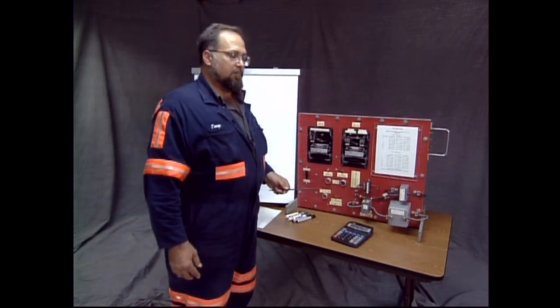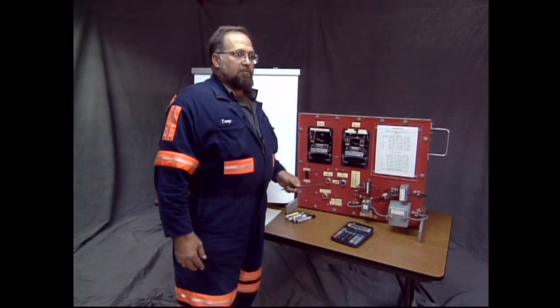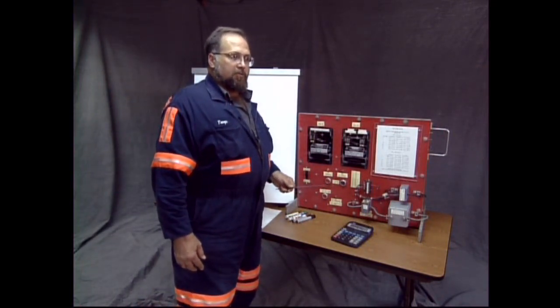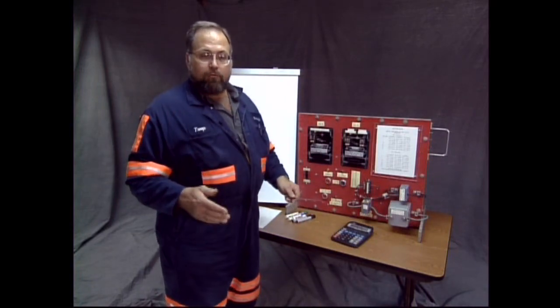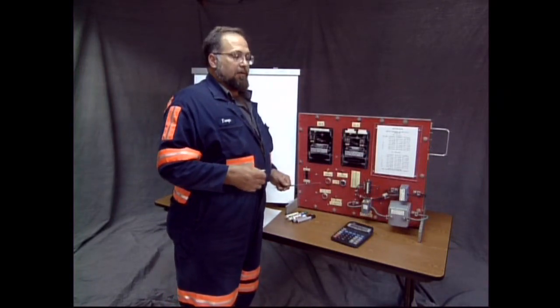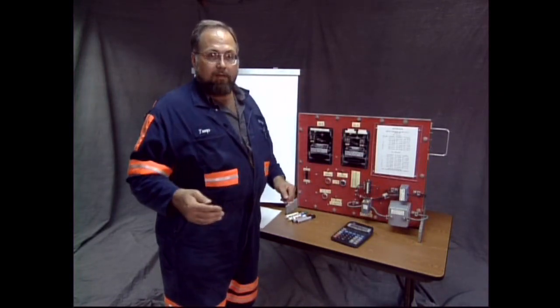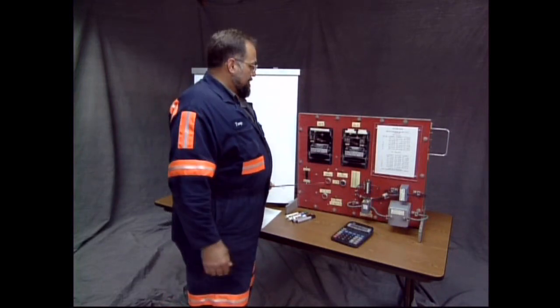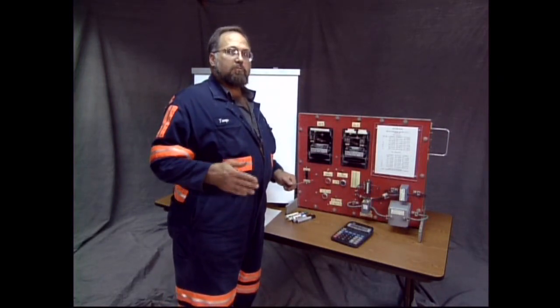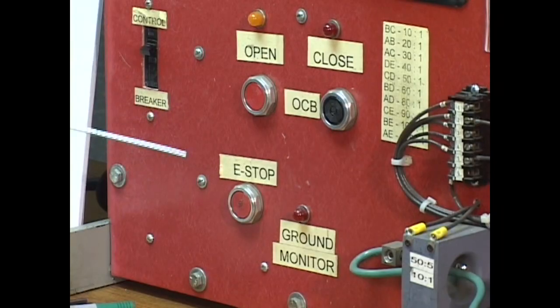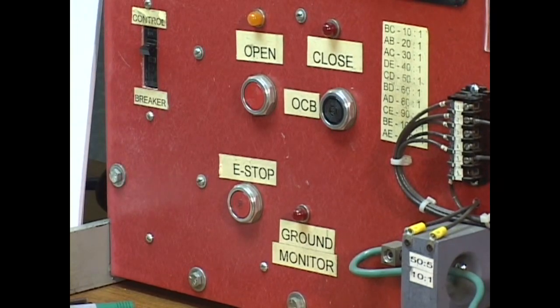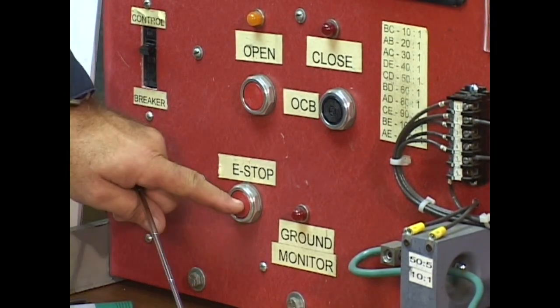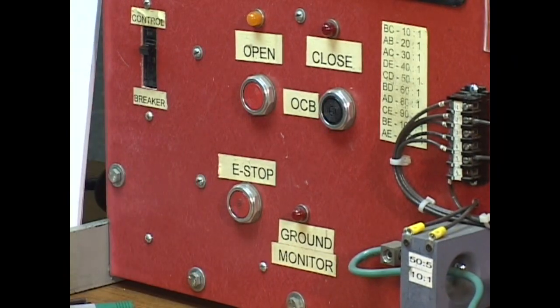Shunt trip does the same thing as a UV, only you have a different application. You put power to a shunt trip, it trips the breaker. On a UVR, you take power away, it trips the breaker. But they both do the same job, you just use them in different applications. And the e-stop, ground continuity monitor wired through the e-stop. You break continuity by pressing the e-stop, the breaker opens.